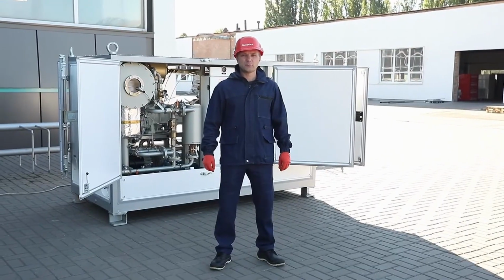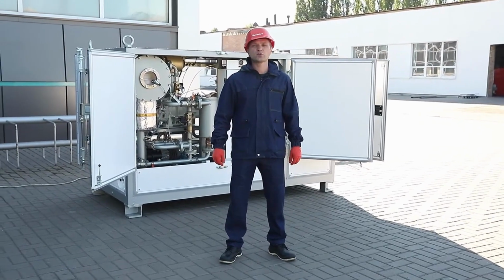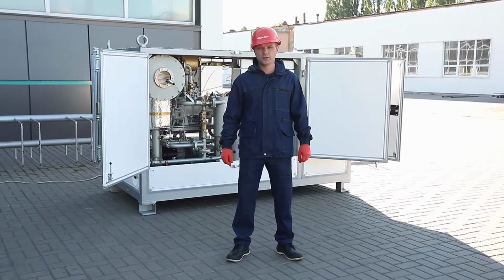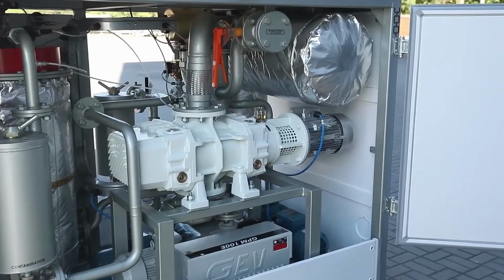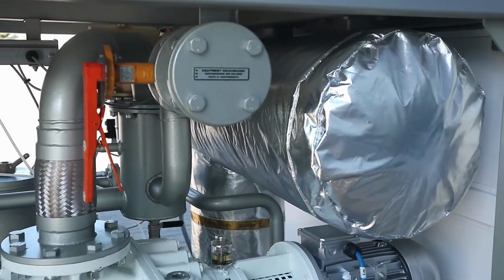Live line processing of oil is justified when more transformers need to be serviced within the same amount of time, or it is impossible to apply a reserve while turning off the transformer is not allowed.